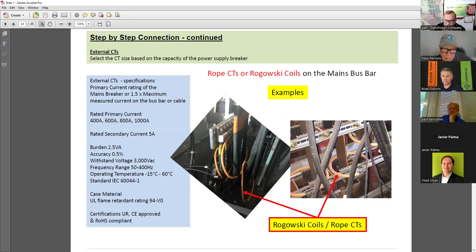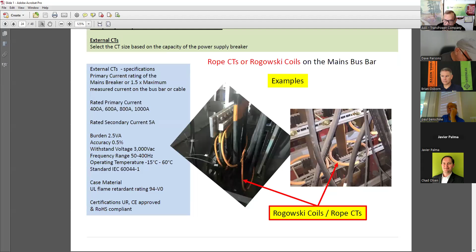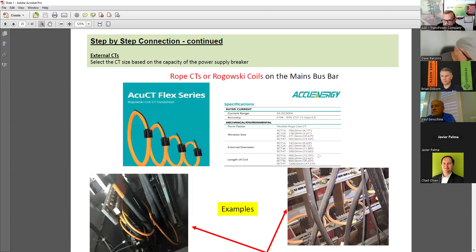So what happens is, when the wires come from the bottom, if you're able to, you put it here. If not, you go a little higher and put it on the bus bar. And if you still can't put it there, the mistake that happens is people go way higher, but then you've gone past the point of common coupling. So instead of installing it here, they installed it there.